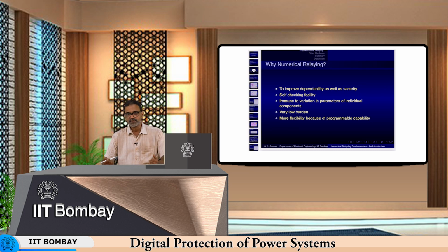You could have data from the other substation because communication is now available with the relays. Earlier, it was not that electromechanical relays had no communication - there was communication, but you required things like couplers to communicate data from one relay to another, or one substation to another. With numerical relays, it is like a computer, so you can hook it up to a network and the relays can communicate.